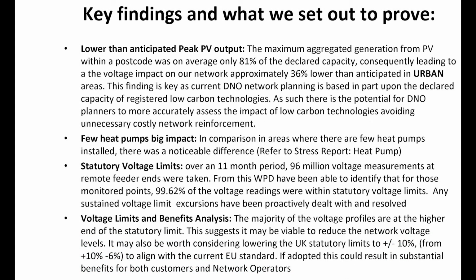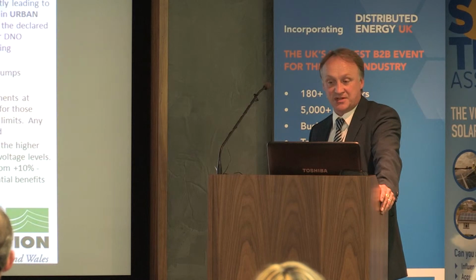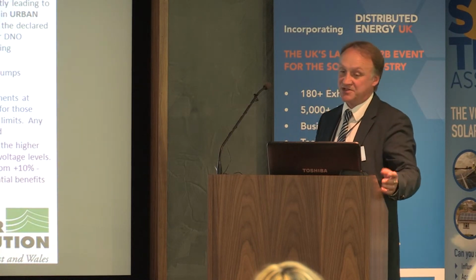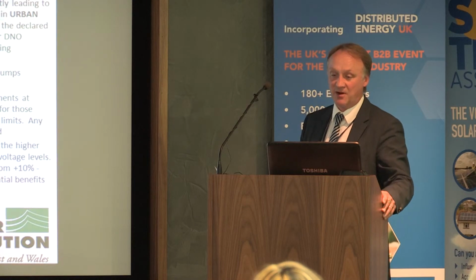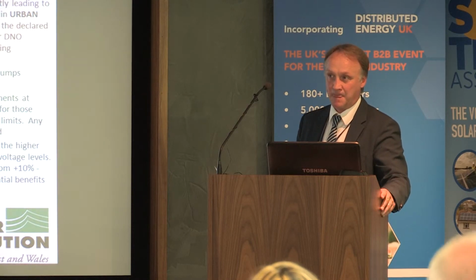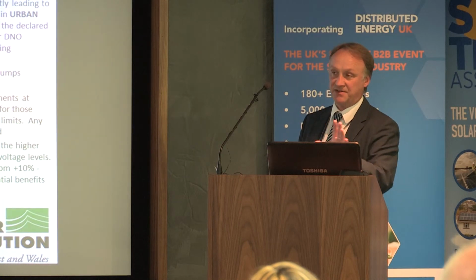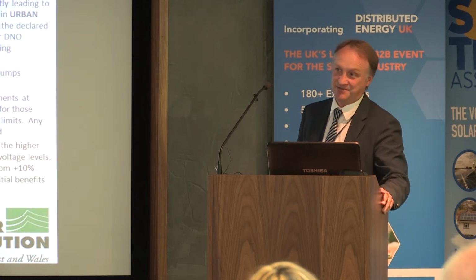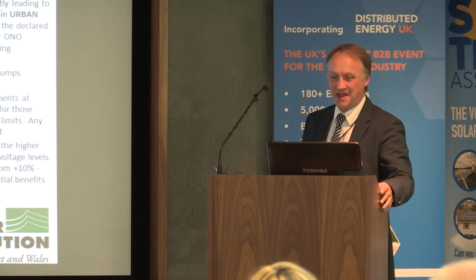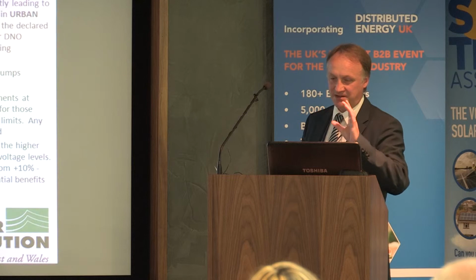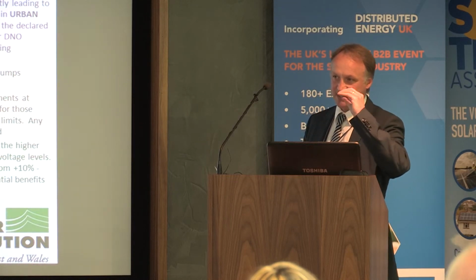Now, the key findings here, bearing in mind this is purely domestic installations. The maximum aggregated generation from PV within a postcode was on average 81% of the declared capacity, leading to a voltage impact on our network which was approximately 36% lower than what we thought it would be. Was that average every year, or? Yeah, and that was over a year. Yeah, last year, which wasn't a good year as far as sunshine goes. But this is peak output, mind. Okay, it's not kilowatt hours. It's the peak. So all we're concerned about is the highest point.